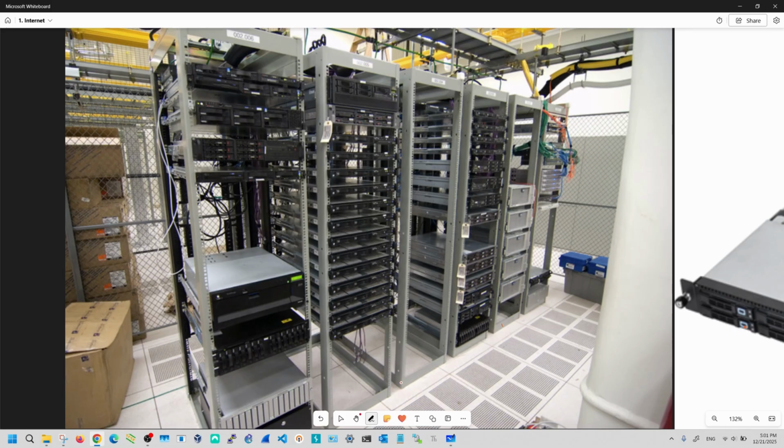Here we can see a typical data center. Servers are installed in these things that are called racks, and these servers have a form that is called a rack server. When you install them, you can push them in and pull them out when you need to replace some defective hardware. On the floor, we can see some holes, some grid. This is called the cold aisle. So you would push out cold air through these holes. The servers would take in this cold air, push it over the components that are emitting heat, and push out the warm air into the warm aisle.